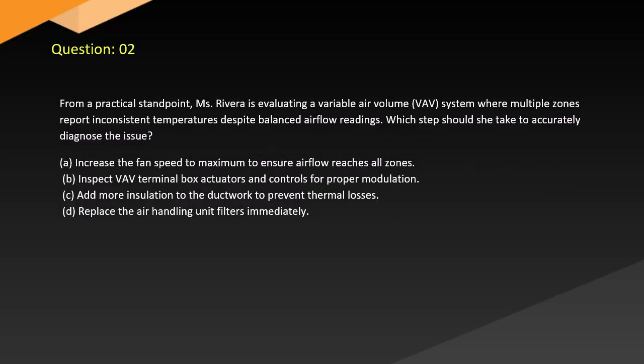Question 2. From a practical standpoint, Ms. Riveros is evaluating a variable air volume (VAV) system where multiple zones report inconsistent temperatures despite balanced airflow readings. Which steps should she take to accurately diagnose the issue? A. Increase the fan speed to maximum to ensure airflow reaches all zones. B. Inspect VAV terminal box actuators and controls for proper modulation. C. Add more insulation to the ductwork to prevent thermal losses. D. Replace the air handling unit filters immediately.